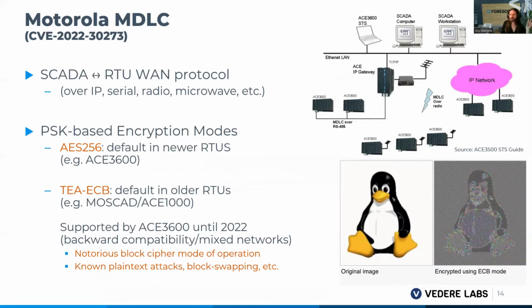Now, in newer RTUs, there's the AES256 modes. In older RTUs, however, including the ACE1000 RTU, which is still widely deployed, there is a mode that is essentially the tiny encryption algorithm in the ECB mode of operation. Now, this mode was also supported by newer RTUs for reasons of backward compatibility, or networks with mixed RTUs, up until recently because of the disclosure.